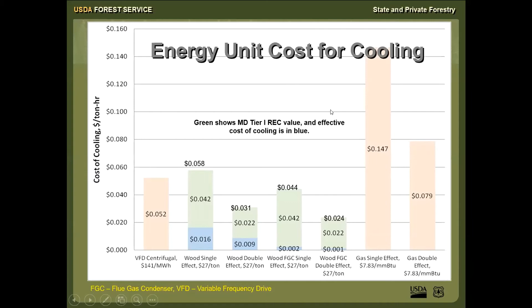But look what happens when we use that steam coming from the flue gas condensation unit and the heat you're harvesting there. It drives the cost of chilling down so that a wood-fired single effect chiller is less than an electric centrifugal chiller by a little less than a penny. And with a double effect chiller, that cost goes down to a little over 2 cents a ton hour, a substantial change. And again, we show what the cost of chilling goes to here in Maryland if Maryland Tier 1 RECs are able to be utilized.